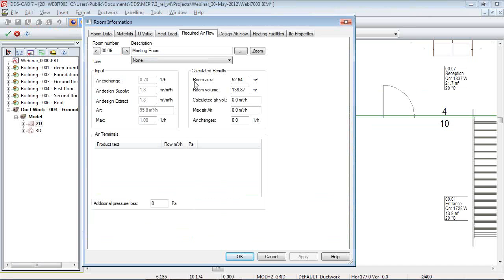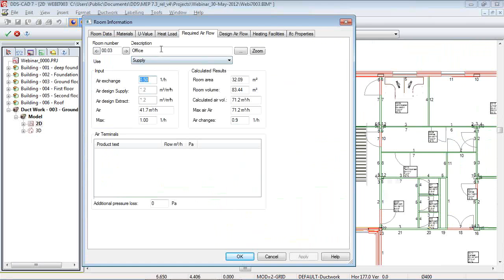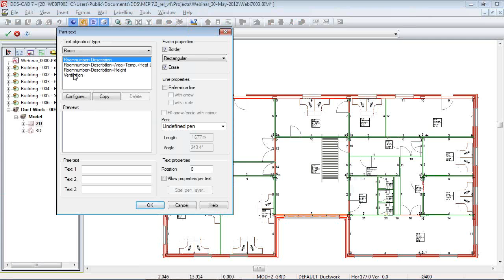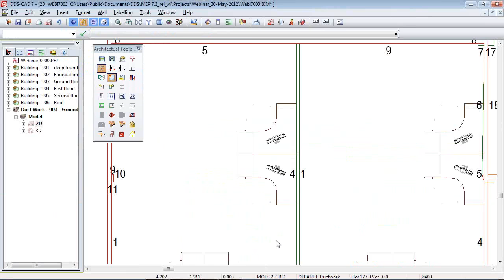We can see the meeting room isn't set to any system for required airflow. But in this office, the function is already connected to supply. What I did before with room text, I can also add on the ventilation side. When I click ventilation and go into a specific room, we can see it needs to be ventilated with 71 cubic meters an hour. This is a direct result of the calculation, and now I can dimension my system based on the airflow requirements of the building type.